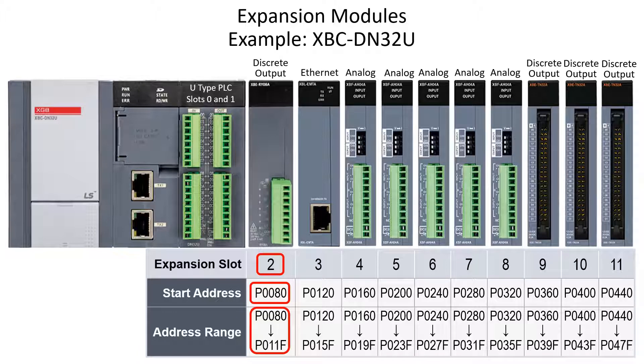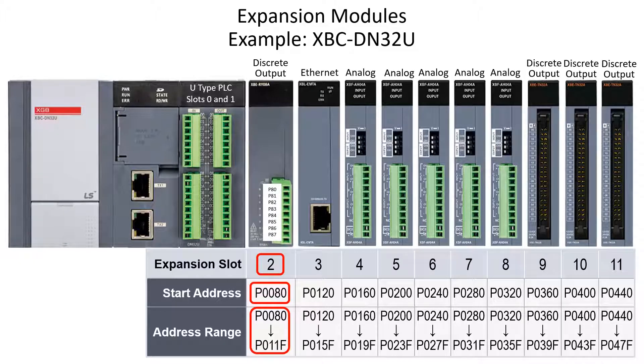In the configuration shown with an 8-point relay module in slot 2, the discrete bit addresses are P word 8 bit 0 through P 8 bit 7. If an input module were installed in slot 2, the first input would also be P 8 bit 0.